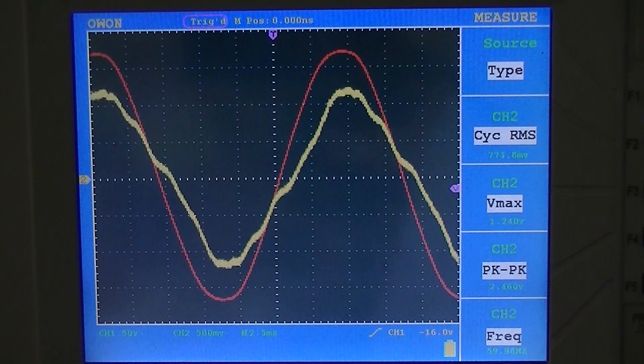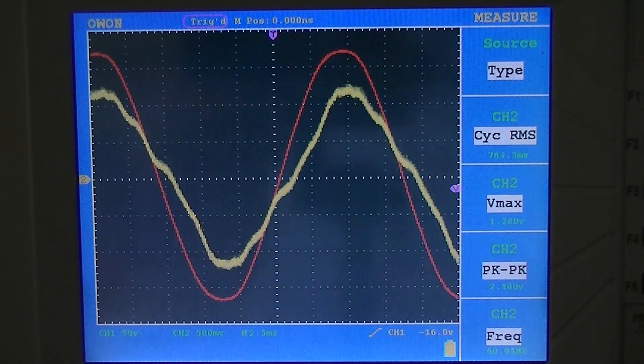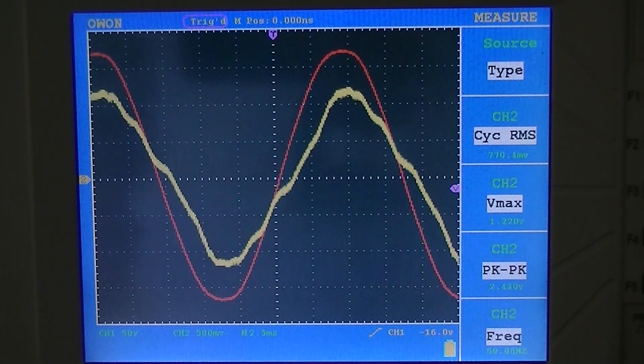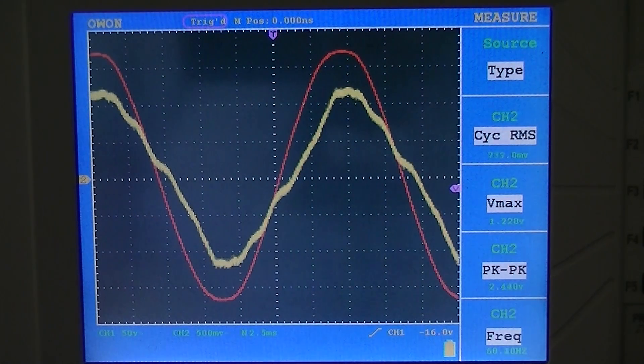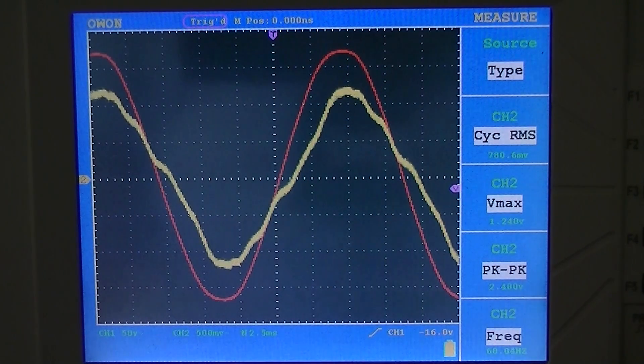So, by noting those values, you can actually run some calculations and establish the actual impedance of the neutral cable. And when you run the calculations, I get a value of 0.01212 ohms.